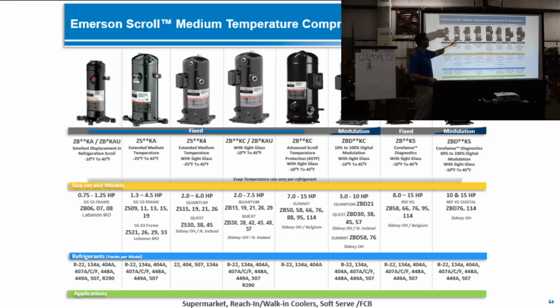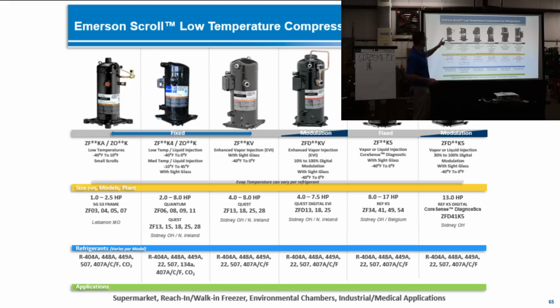So I'll go to refrigeration. Another 1, 2, 3, 4, 5, 6, 7, 8 for medium temp. And then 1, 2, 3, 4, 5, 6 for low temp. That's over 20 different scrolls, different capacities. They work differently. Some have liquid injection, some don't. Some do high temp, some do low temp. It's important, yes, I know how a scroll works, but how does that scroll work? That's the important part. Does it have an internal pressure relief? You know, how is it protected? We'll talk about that stuff today.